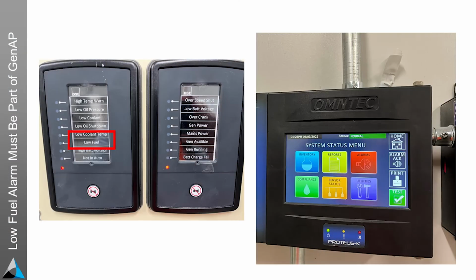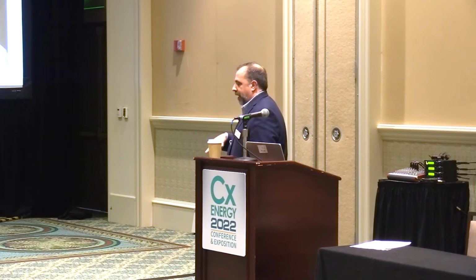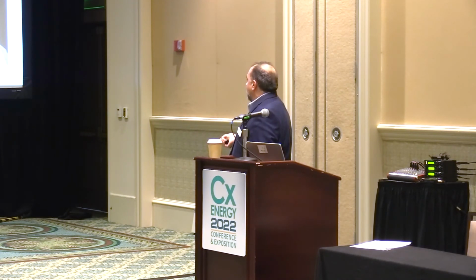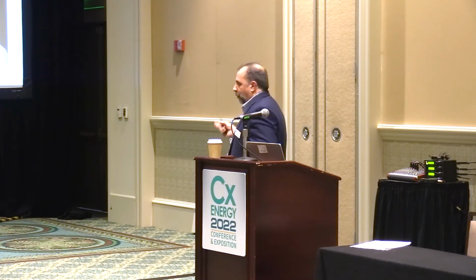Then we also test, as part of the whole emergency power testing, the remote annunciators, like I said. And the reason, again, that I'm looking for, is there an alarm for low level in the main tank? The reason sometimes they decide not to wire that is because there may be a main fuel system monitoring system annunciator, very nice panel. I don't know why fuel guys get the nice, pretty looking things and we get these. So we're sitting right next to these panels, and it says when the system is low.